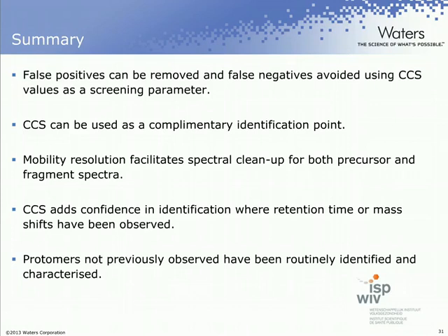Okay, and I think the final question we have today, Mike, is what advantage does ion mobility and the CCS approach give over high resolution, for example, over 100K? Well, David, we have some very unique advantages because we are uniquely resolving on size, shape, and charge. For example, there are advantages when dealing with isomers, conformers, and protomers, and in this case, no matter how much mass resolution you have, they won't be resolved.